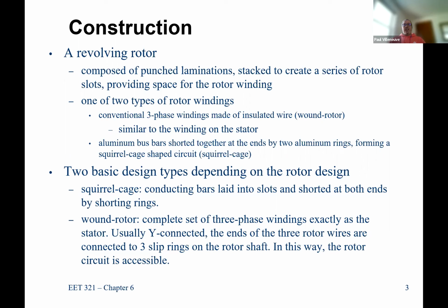There's a very specific title for it. Anybody want to guess? You can take a look on the internet, but it's called a DFIG. It's a doubly fed induction generator, which is basically just a wound rotor machine. So you have these 3-phase windings on the rotor circuit that you have to bring out, and you use a bunch of brushes and slip rings to access those rotating parts. But it's a very similar design to my stator winding.